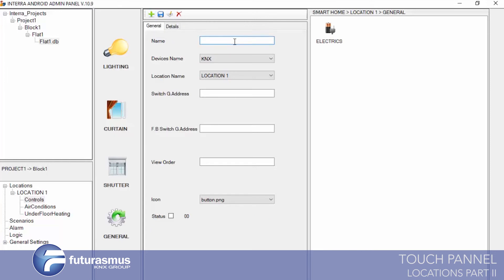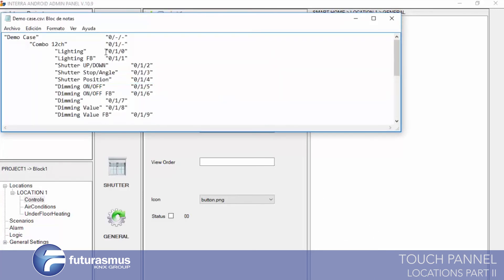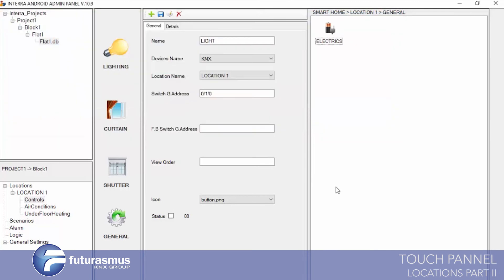We can also define another one with KNX — for example, adding a light with an address. We are giving the address from the combo: lighting address 0/1/0 and lighting feedback 0/1/1. Also giving the view order. Note that reverse output is only related to outputs, so you cannot use it for KNX jobs. And save.